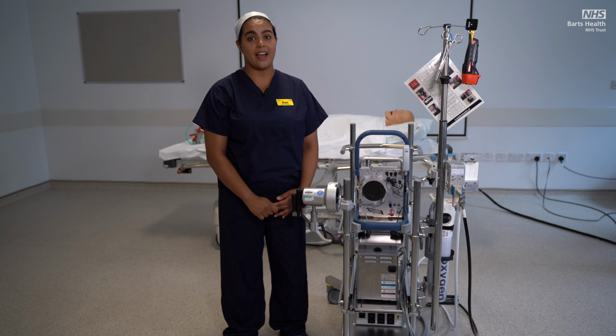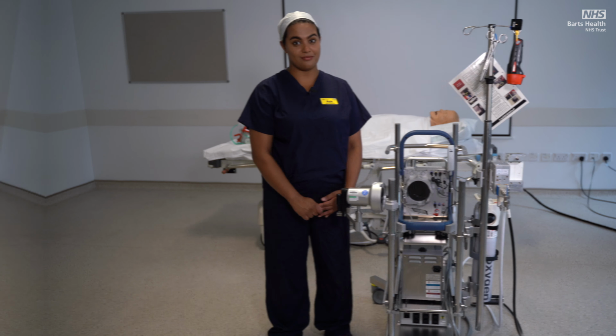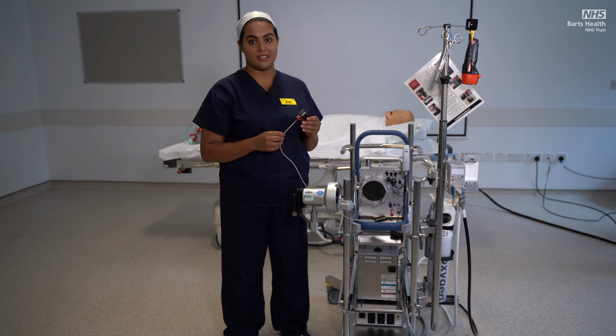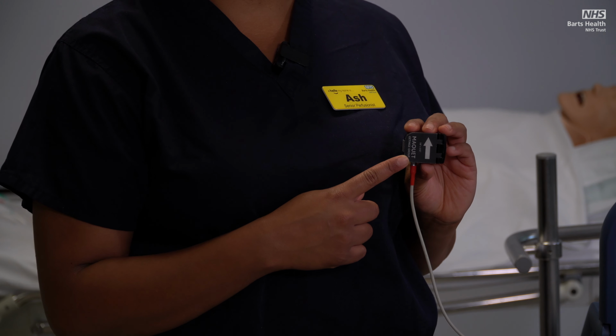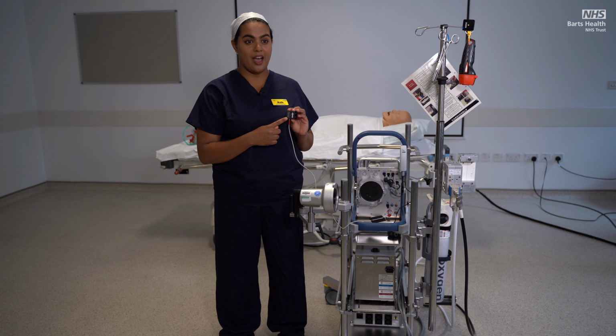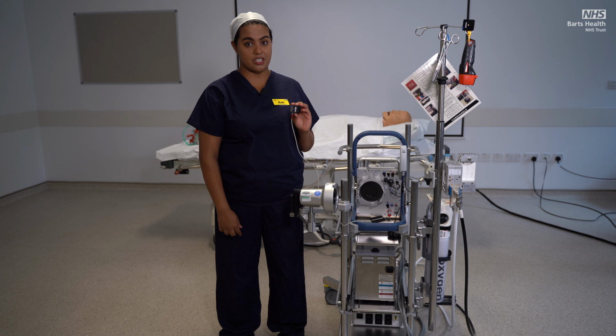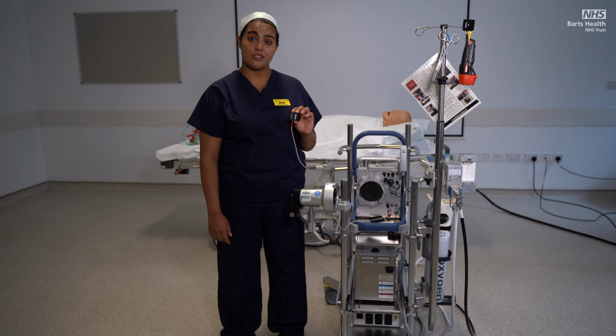The Cardiohelp has 4 integrated sensors to monitor the status of the ECMO. This is the flow and bubble sensor. The red tape at the join indicates it's an arterial monitoring sensor. The arrow on the sensor indicates the direction of blood flow and must be placed on the return line 30 centimeters away from the oxygenator and towards the patient heart. As well as monitoring arterial blood flow, this sensor also detects bubbles in the arterial line.